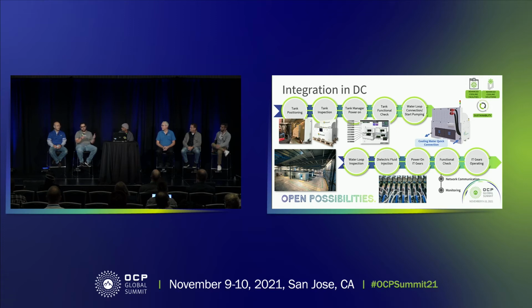So switching to, or bringing Immersion into, say, air-cooled or a cloud-native hyperscale data center does have new elements compared to what we do today. Starting with tank positioning: today with air cooling we have hot aisle, cold aisle configuration, containment, and all the stuff around airflow management. Now we don't have to think about that anymore. Instead, bring the tank as close as possible to your physical power or cooling connections.